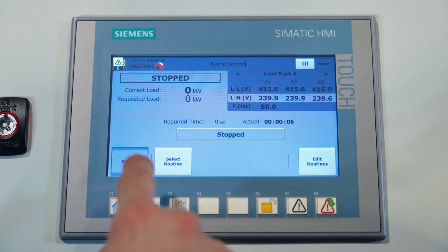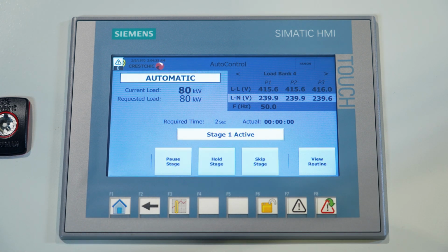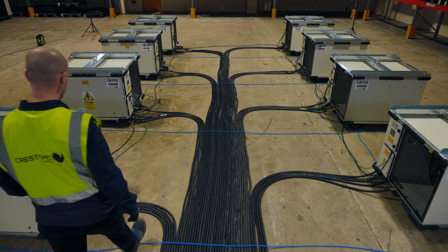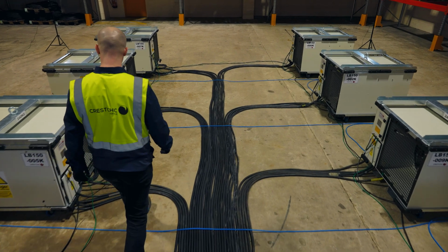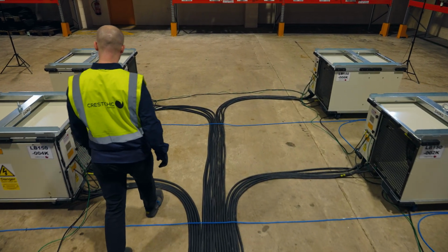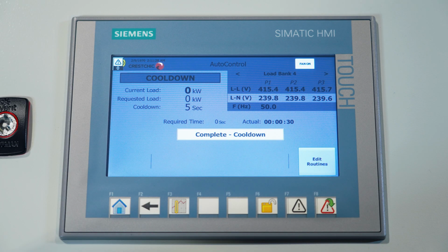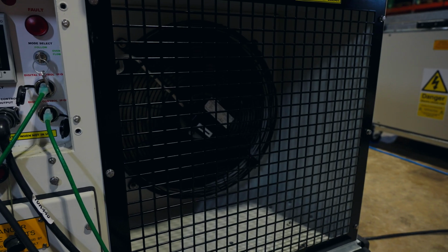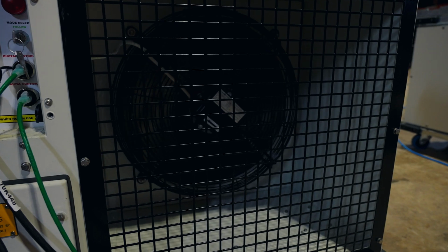In this example, we have created a program to put 80 kilowatts on for 2 minutes, 150 kilowatts for 2 minutes, and full load of 300 kilowatts for 5 minutes, then back down to 150 kilowatts for 2 minutes before all load is then removed. You can see the operator is observing the test only, checking instrumentation and the equipment being tested is functioning as expected. Once the automatic test is complete, the load banks will shut down after a necessary 4 minutes cooldown.